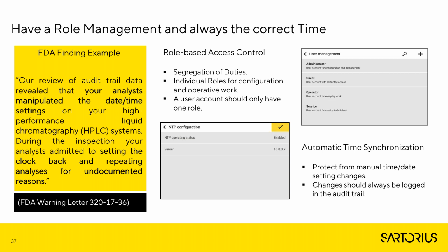This illustration also highlights the significance of timing properly. Manually changing the system date and time should no longer be the case when working with modern network devices. The instrument's time can always be adjusted with the help of automatic time synchronization. And this is crucial because all computer systems, after some time, will show some clock drift. That means the system time eventually deviates from the accurate, real time. On Cubis II, it is possible in a few steps to synchronize the device's date and time with the help of an available network time server. Next slide, please.